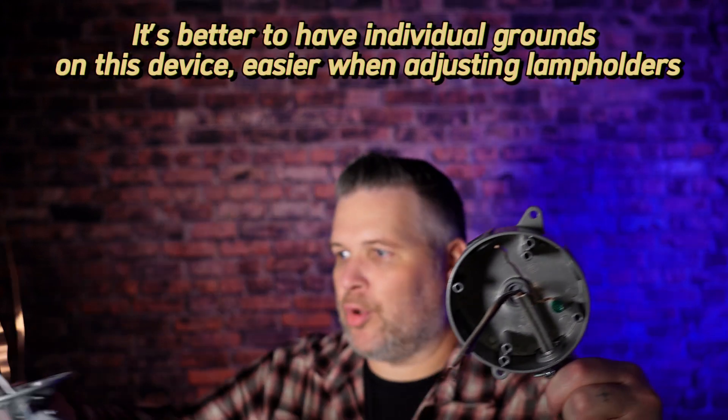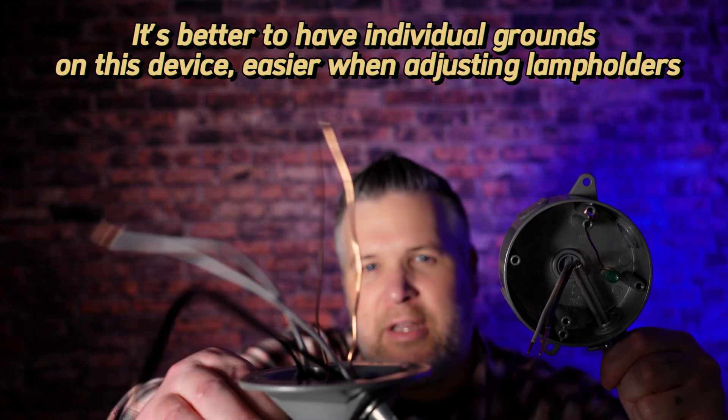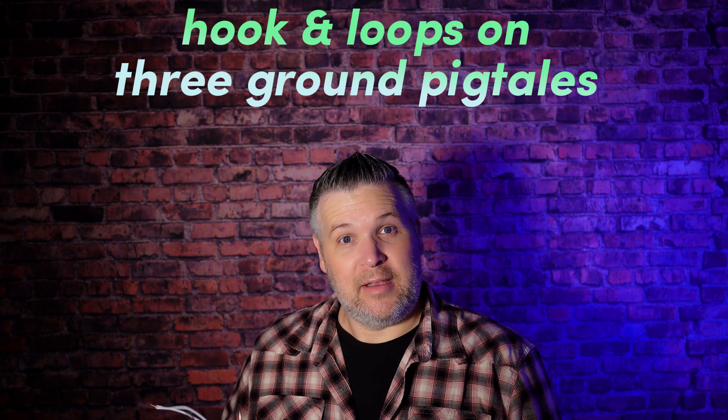Here's the UF cable — once you have it in that box like that, you just pull and it's already done the work for you. So that was UF cable. Now I have my individual ground — I told you I was going to show you that. This is my individual ground in that box, and I made individual grounds for both of the lamp holders because they do have the green screws there. If your house ever gets struck by lightning or something like that, you're going to wish you hooked these grounds up. If the grounds are hooked up right in a home, instead of it blowing out at the lamp holder or damaging some equipment, the electricity will be sent to the main panel and down through the ground rod — and most likely these will work again. This is properly grounded like the manufacturer intended.